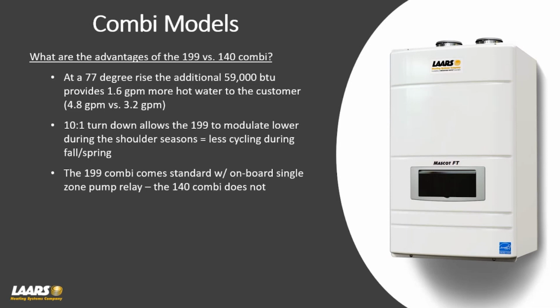So now the 199 also comes standard with an onboard single zone pump relay. So we talk about primary, secondary, especially if they're using zone valves, you're going to have a system pump. We give you those contacts right in on the terminal strip. So that's an addition to it. Now they don't have to buy an additional pump relay or what have you. So that's all added in.